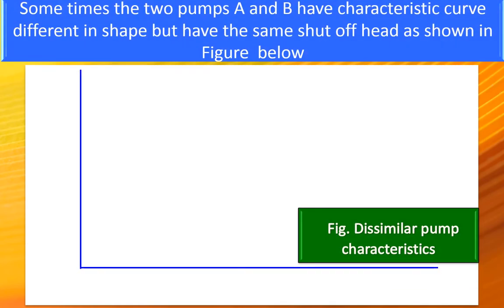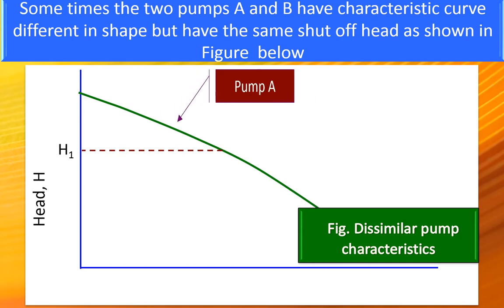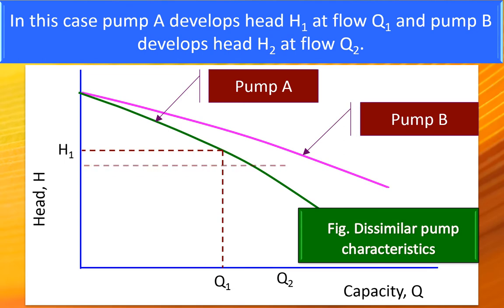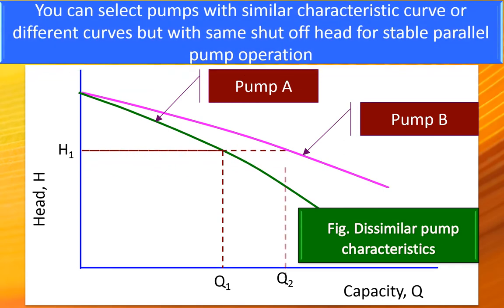Sometimes the two pumps A and B have characteristic curve different in shape but have the same shutoff head as shown in the figure below. In this case, pump A develops head H1 at flow Q1 and pump B develops head H1 at flow Q2. You can select pumps with similar characteristic curve or different curves but with same shutoff head for stable parallel pump operation.